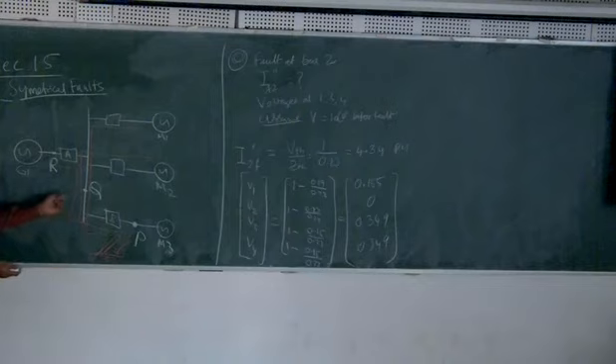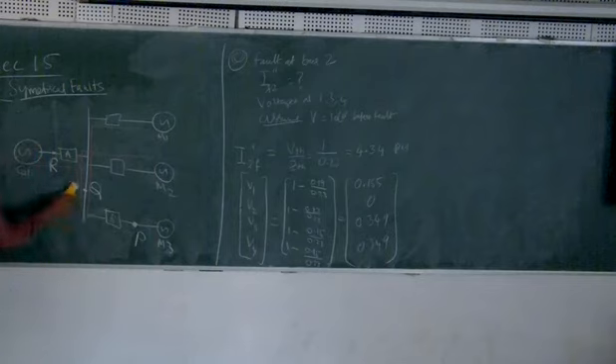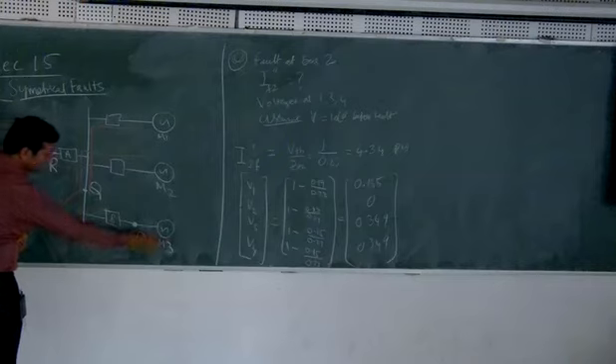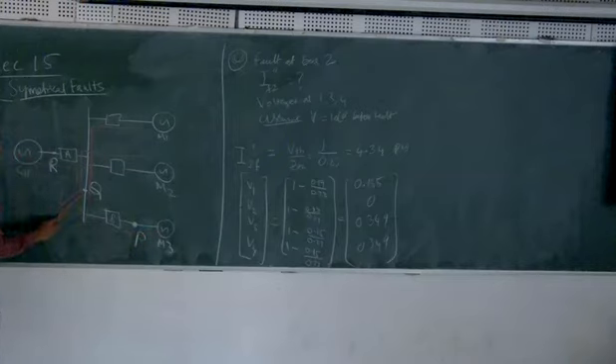What if the fault is at Q? What happens if the fault is at Q? When the fault is at Q, there will be one fault current like this, another like this, another like this. From machine 3, it will come like this, and then another fault current like this. So all four have a fault current through these circuit breakers. So if there is a fault at Q, which circuit breaker should open?